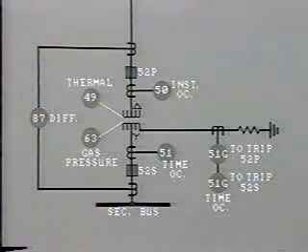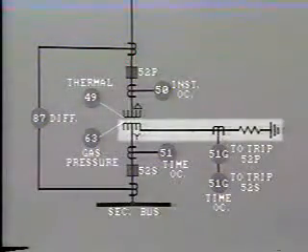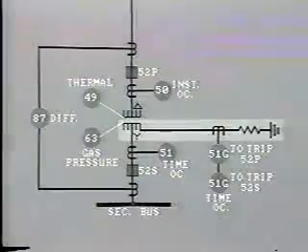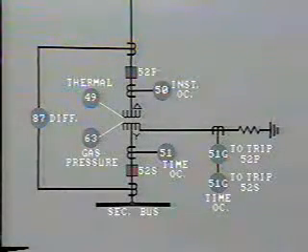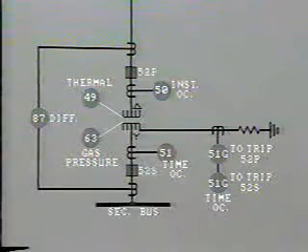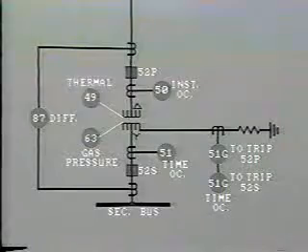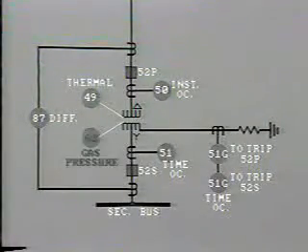What else does the diagram tell us? We can see that the primary is delta connected and the secondary is Y grounded through a resistance. The circuit breakers are represented by 52P (primary) and 52S (secondary). Looking up our reference list, we find that the transformer itself is equipped with a thermal relay, 49, and a gas pressure relay, 63.